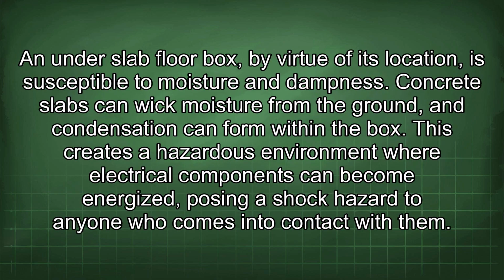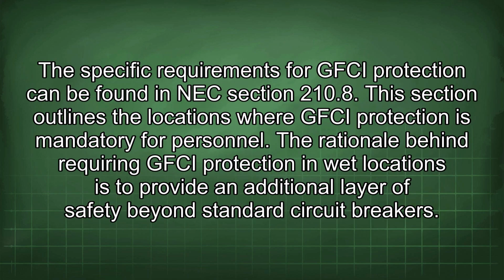An under-slab floor box, by virtue of its location, is susceptible to moisture and dampness. Concrete slabs can wick moisture from the ground, and condensation can form within the box. This creates a hazardous environment where electrical components can become energized, posing a shock hazard to anyone who comes into contact with them. The specific requirements for GFCI protection can be found in NEC Section 210.8. This section outlines the locations where GFCI protection is mandatory for personnel.